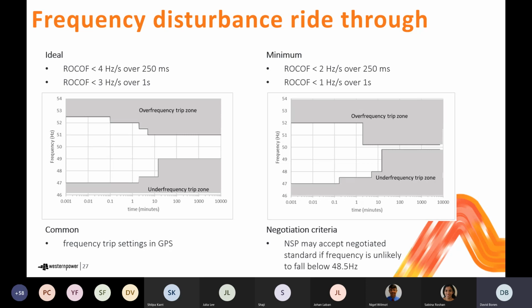The ideal requires the generating system be able to survive and continue to operate for a greater rate of change of frequency than the minimum. So at the ideal level, you're talking about up to 4 hertz a second over the first 250 milliseconds following the disturbance, and the minimum is half that at 2 hertz a second over the first 250 milliseconds.